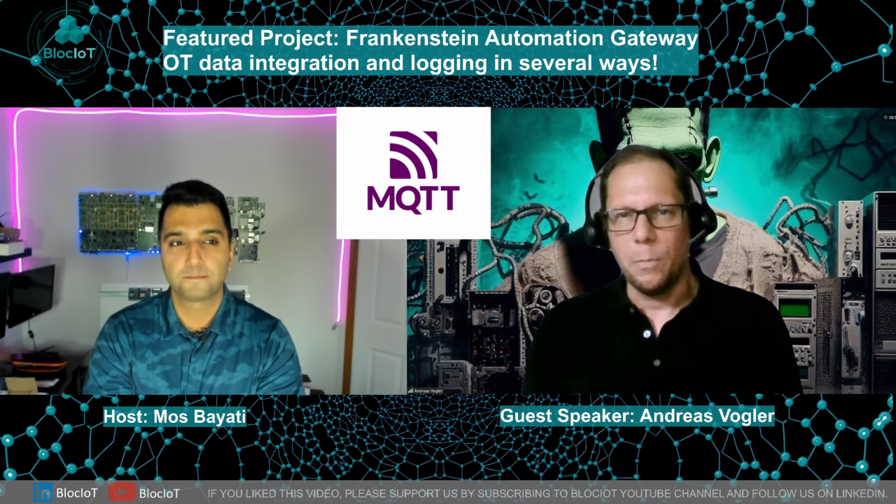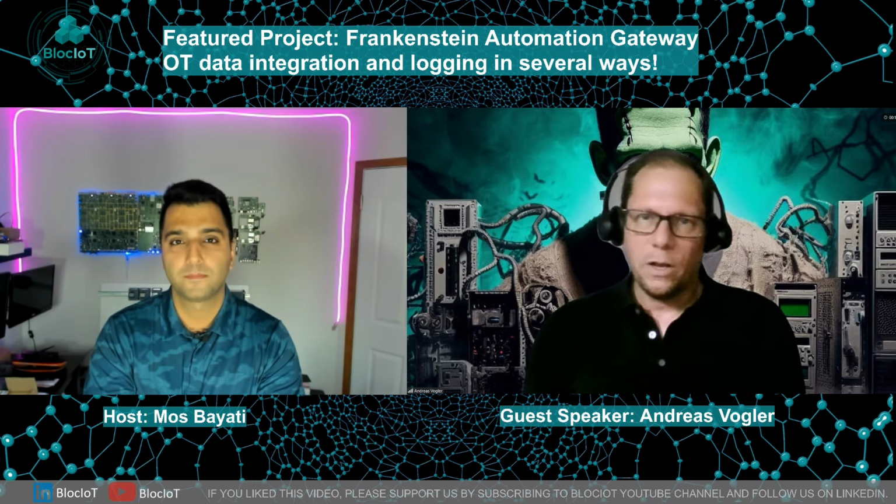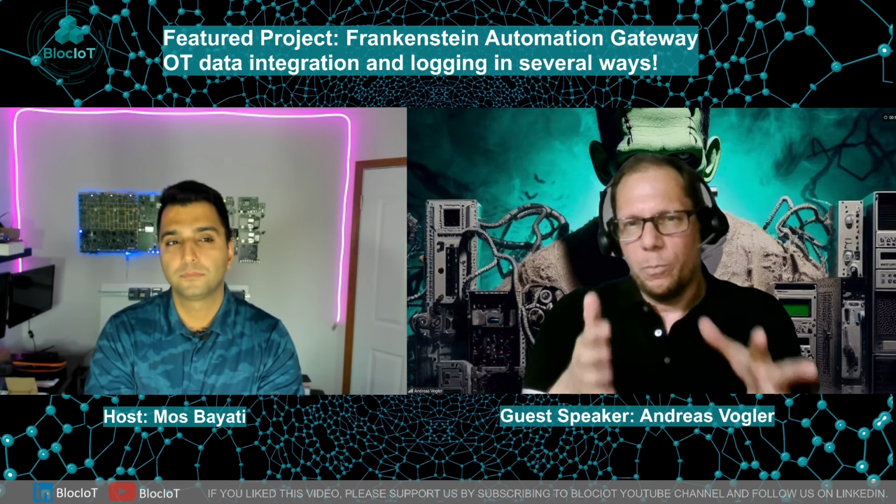And then, because I did a lot of work with MQTT brokers also in proofs of concept, I thought, hey, MQTT is so easy to use. In every language you have simple libraries, just connect, publish, and subscribe, and you can do crazy work with it. And then I also thought, let's make an interface in the gateway so that it acts as an MQTT broker, somehow. But the point is, when you subscribe to a topic, and the topic has to follow rules in the naming, then behind the scenes a connection is opened to the OPC UA server and the subscription is done. So then the data is passed through and you get it as an MQTT client.